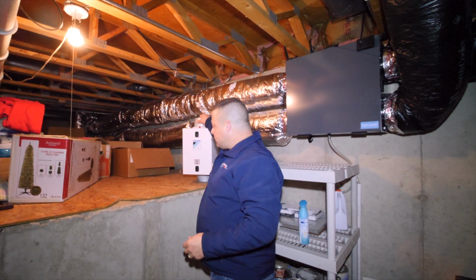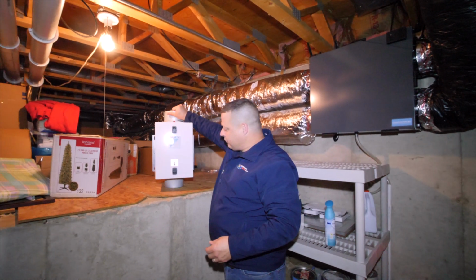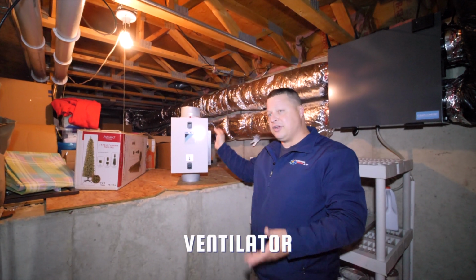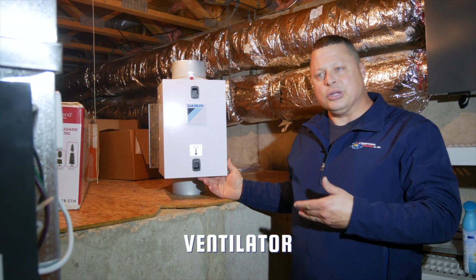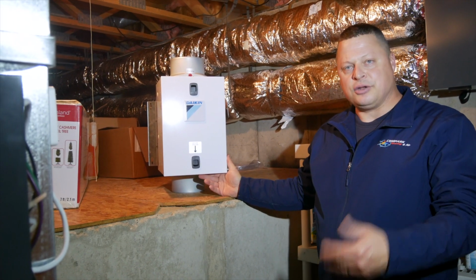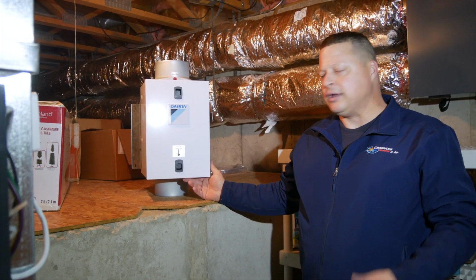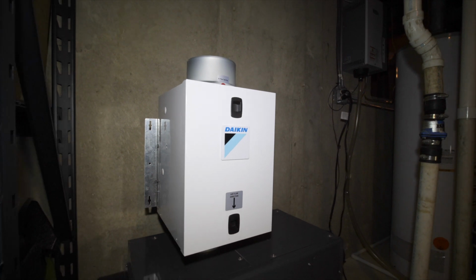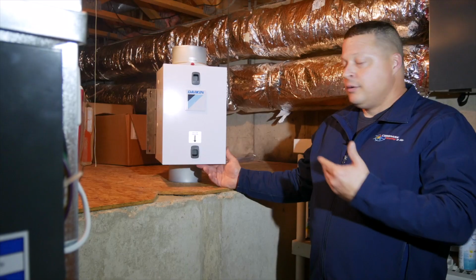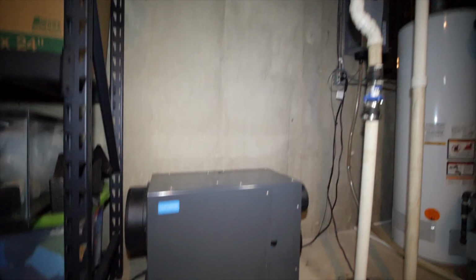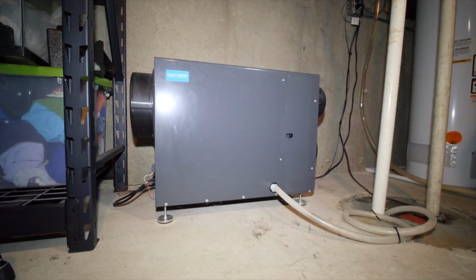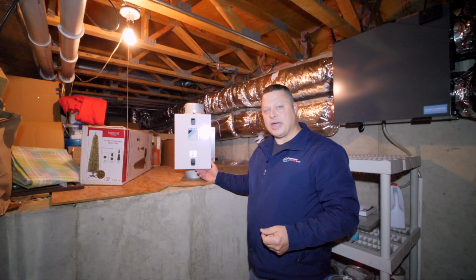Another way you can do that, and I brought this in specifically just to be able to talk about a ventilator, you would use this. It is a little less costly to use just the ventilation as opposed to an ERV or HRV, but you bring fresh air in at the rate that is for your specific home. This is one, for instance, we would run through the dehumidifier so you don't have the hot, humid air coming directly into the house in the summertime.